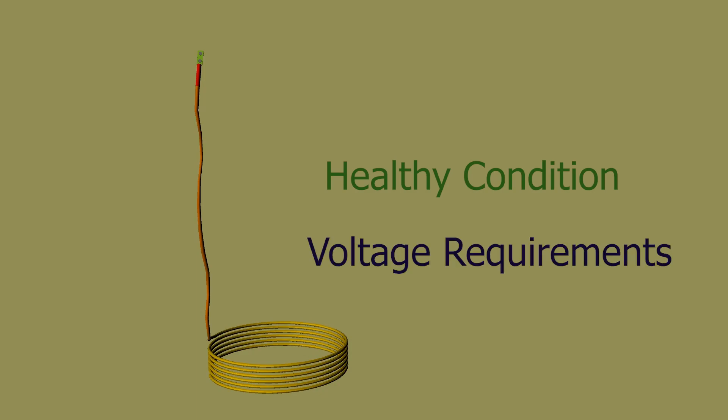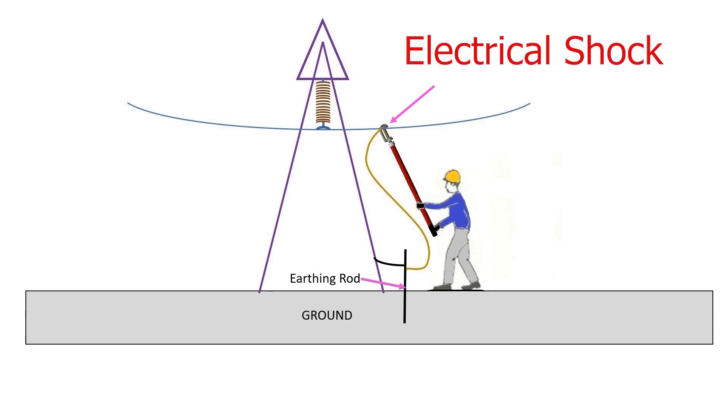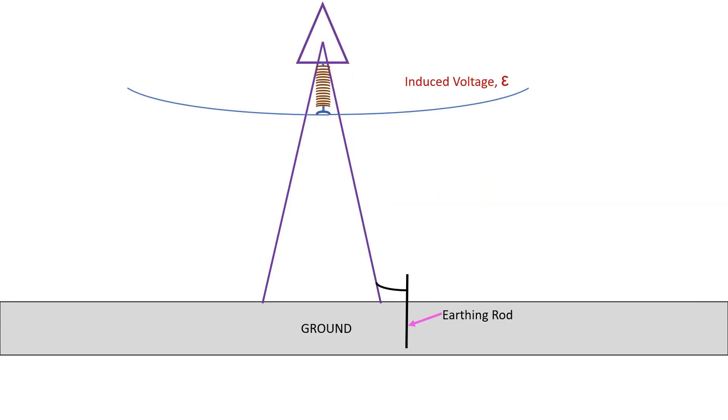When applying PTG, always connect cable with the ground first and then to the line. This is done to avoid any risk of electrical shock, because if there are induced voltages in the line and the worker connects the grounding cable with the line first, the worker can be subjected to electric shock.